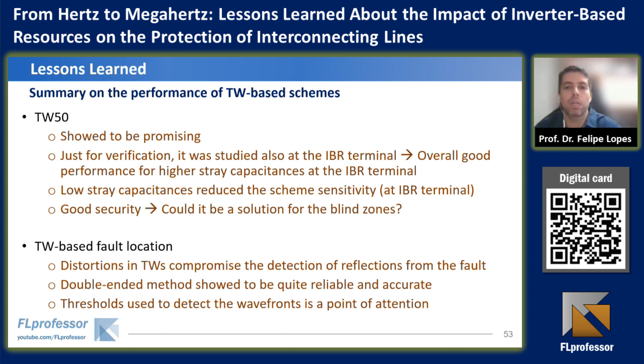And finally, regarding the traveling wave-based fault location methods, we tried to apply both double-ended and single-ended methods, but the double-ended presented better results because detecting the reflections after the distortions caused by the transformer at the IBR terminal is a little bit difficult. So the double-ended method showed to be quite reliable and accurate, as accurate as it has been in traditional systems, but the threshold used to detect the wavefronts is undoubtedly a point of attention that must be taken into account.